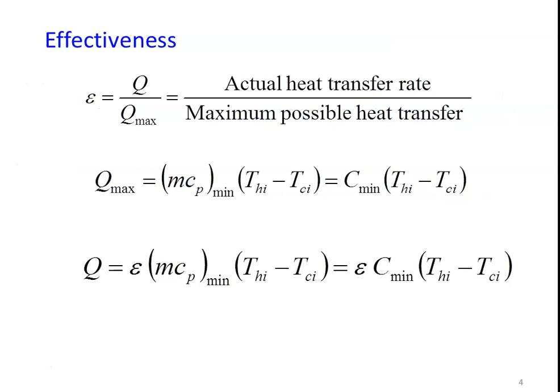We define first the Effectiveness of the Heat Exchanger. Effectiveness Epsilon equals Q divided by Q maximum — the Actual Heat Transfer Rate in a Heat Exchanger divided by the Maximum Possible Heat Transfer. The actual heat transfer is calculated as m·Cp·ΔT for the hot fluid or the cold fluid. Q maximum equals C minimum into the Maximum Possible Temperature Difference, where Thi minus Tci is the maximum possible temperature difference.